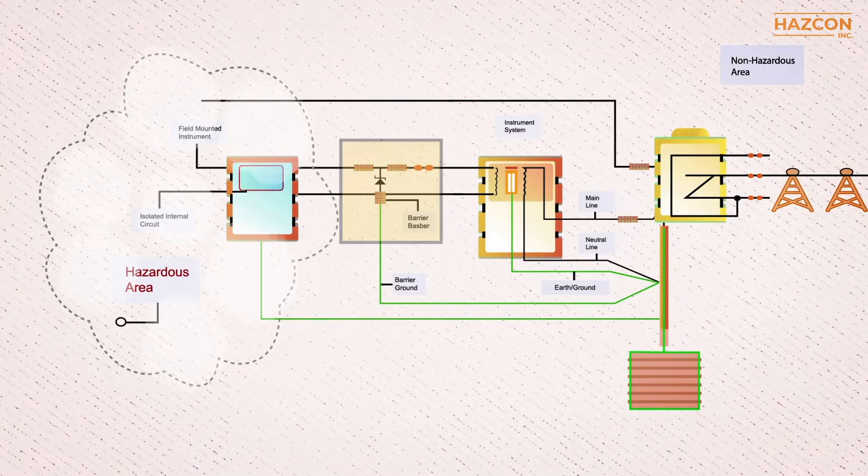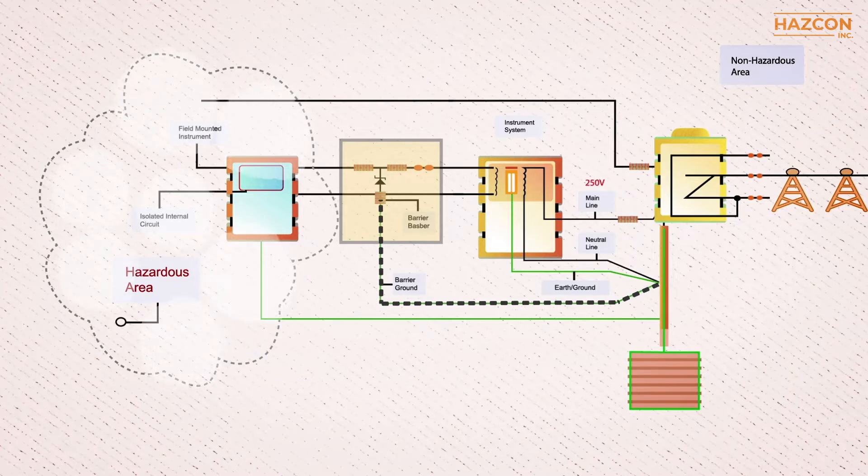They limit power to the field device in the hazardous area and must be grounded properly in order to direct the fault current to the main referenced grounding point, thus limiting the voltage and current output of the field device to safe levels for the given environment.